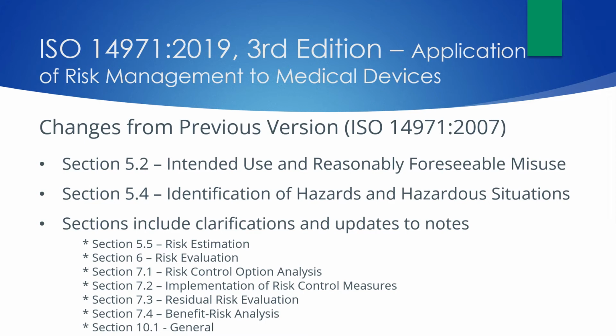There are a number of additional sections listed here that include clarifications and updates to notes within those sections. One section we're going to touch on is 7.4, which is the benefit risk analysis. This section has strengthened language around benefit risk analysis, reflecting a growing area of attention by regulatory bodies in evaluating compliance. Monitoring benefits is also important for post-production activities to determine whether the benefit-risk balance changes over time to adjust the risk management process accordingly.